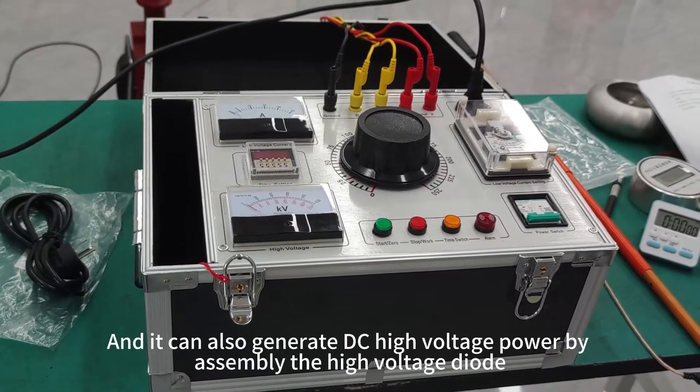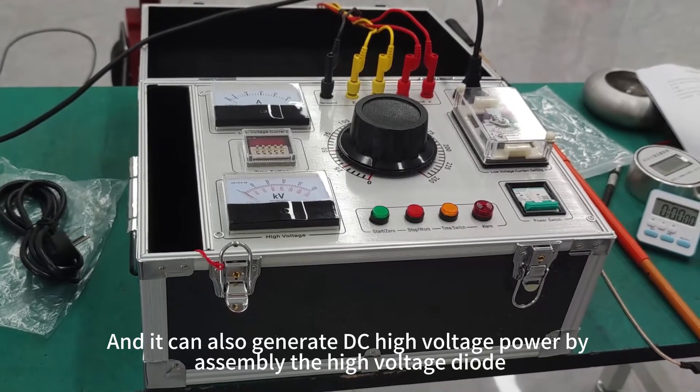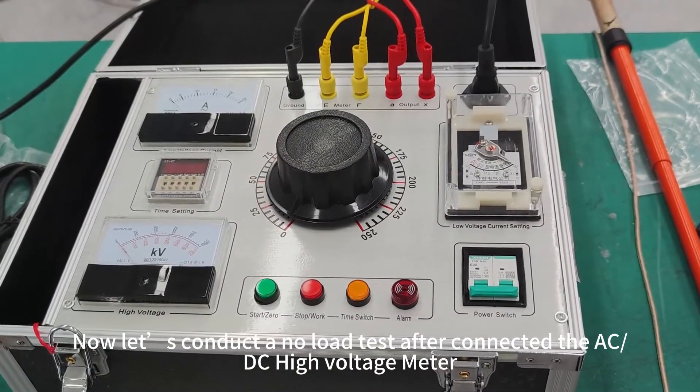And it can also generate DC high voltage power by assembling the high voltage diode. Now let's conduct a no-load test after connecting the AC or DC high voltage meter.